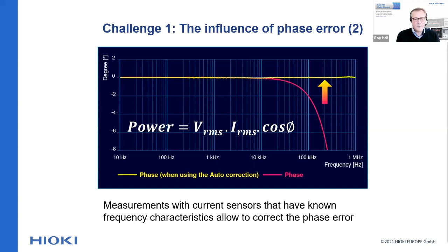Hioki is predominantly using external current sensors that have a 2-volt output voltage for the nominal input current. This type of current sensor will cause a phase error, as you can see in this frequency diagram. The red curve shows that already from about 10 kilohertz, there is a noticeable phase error, and therefore you might consider that this current sensor is not a good solution for high frequency power measurement. But that's not really the case. Let me explain why.